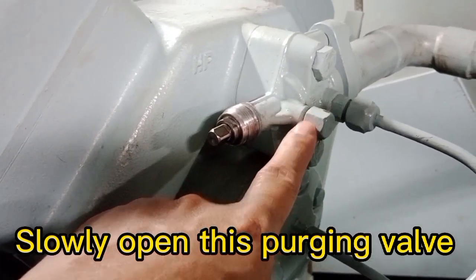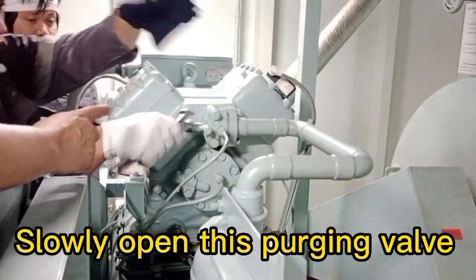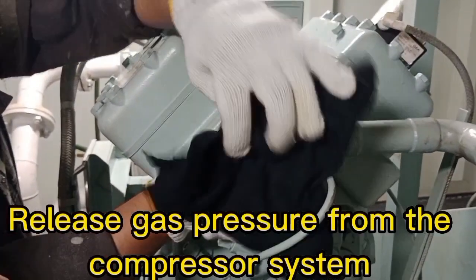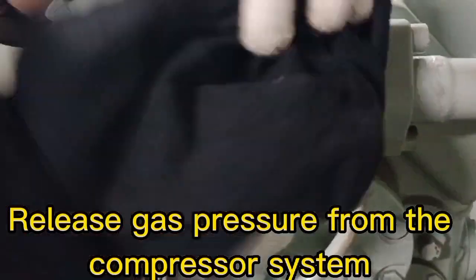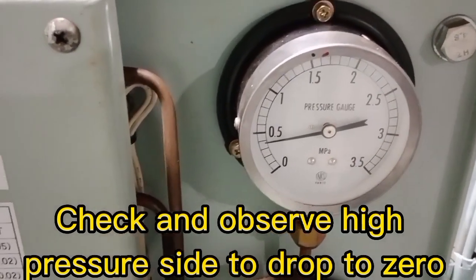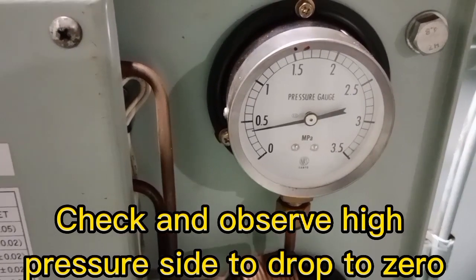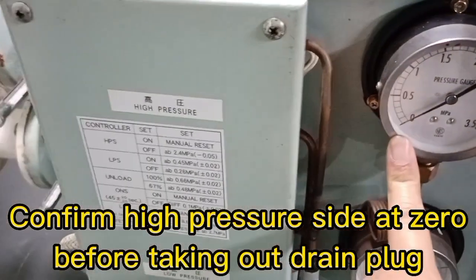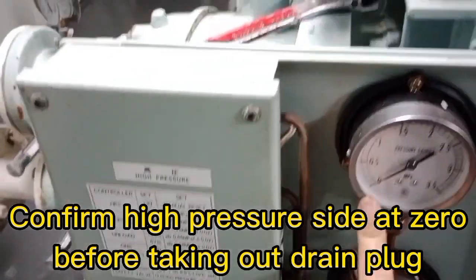Check and confirm the liquid level at the condenser side glass is slowly increasing. Next, slowly open the purging valve to release gas pressure from the compressor system. Check and observe the high pressure side to drop to zero, and confirm high pressure side is at zero before taking out the drain plug.